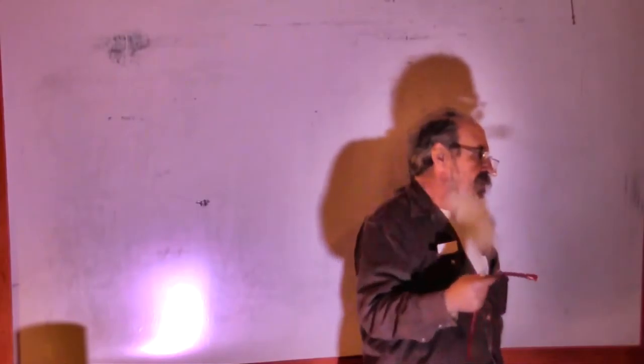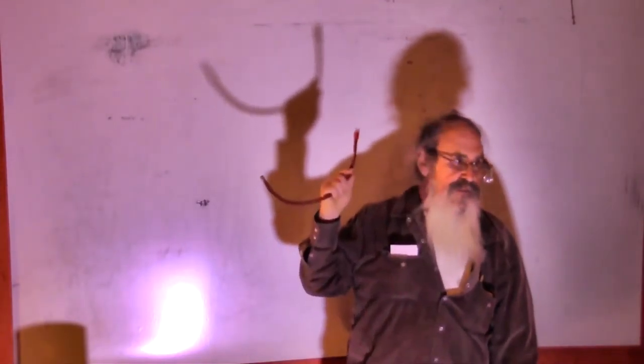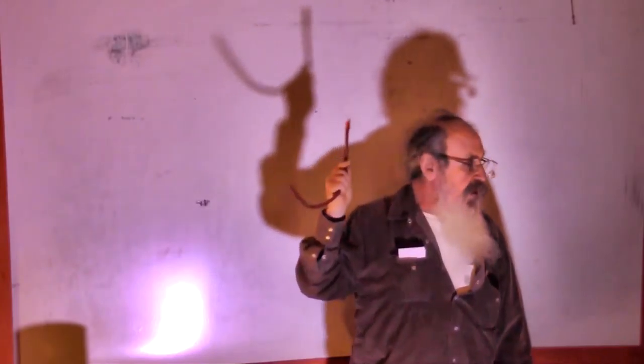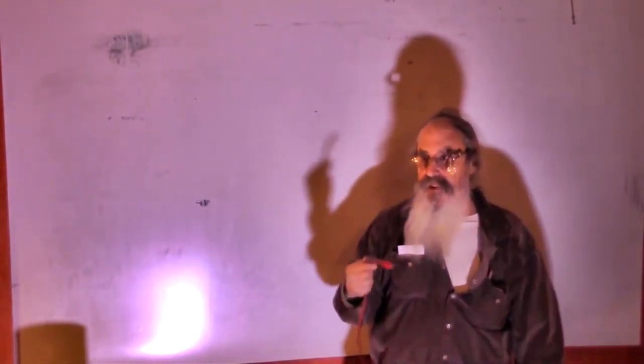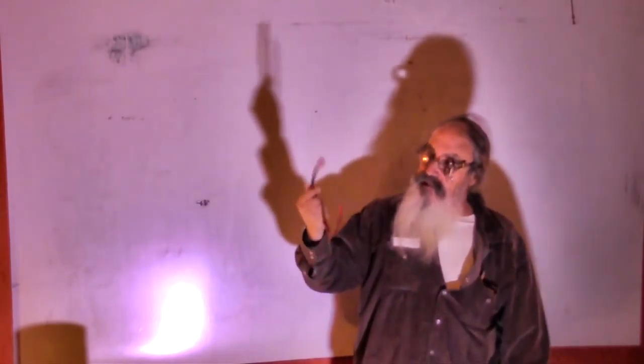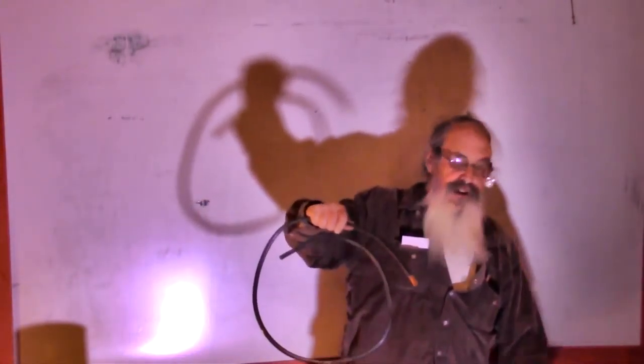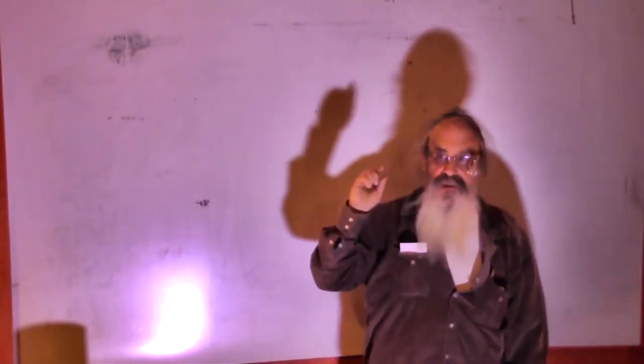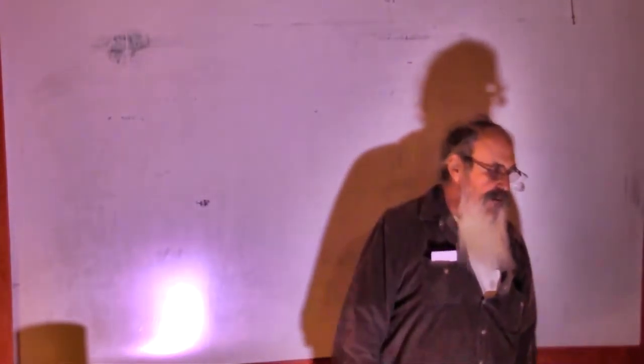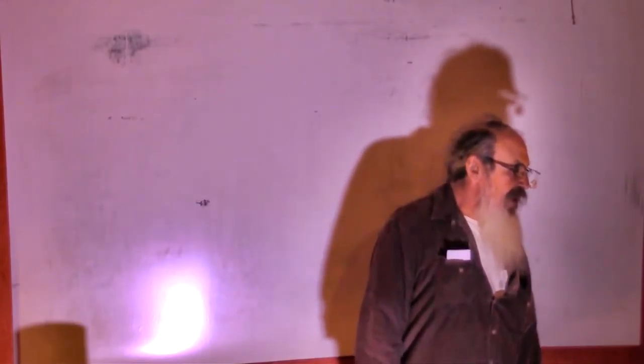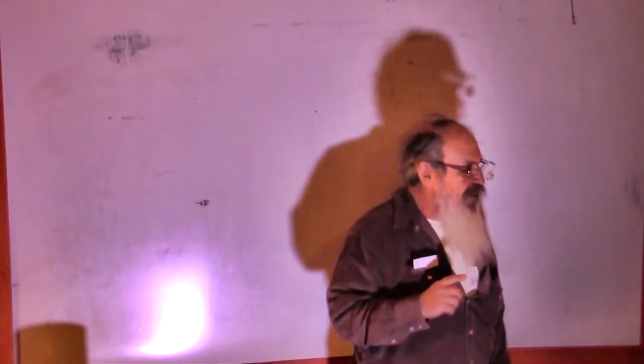So this is what I've used for my cabin out in the mountains, from the battery to the inverter, because that may be carrying 50, 75, 95 amps. It's expensive stuff, but it's easier to use because it's flexible. The equivalent THHN wire would be much harder to deal with because it's not as flexible. So: high amperage, fat wire. Because if you use skinny wire with high amperage, you get heat, and that's what ends up burning your house down. Is that a clear answer to why you need at least some grasp of amperage?